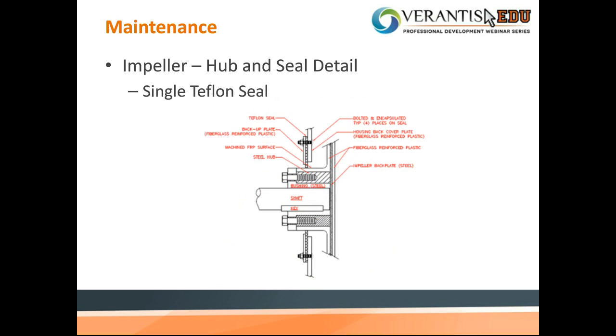The maintenance on the impeller and hub seal. Basically, this is a picture of the hub seal detail. This particular arrangement has a single seal, but if you've got a different seal arrangement, review the seal. Make sure it's still doing what it's designed to do, and also check the bolts to make sure the bushings are still tightened.